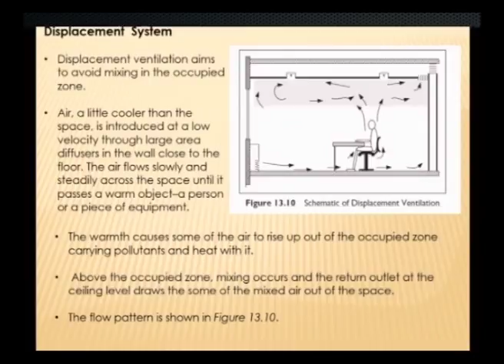The air movement in the space separates into a lower displacement zone with a recirculation zone above. In a well designed space, the recirculation zone is just above the occupied zone. So, the objective of the system is to have the occupants and the equipment in a flow of clean air with their own heat causing convection around them. This will lift their pollutants up out of the occupied zone. So, usually the pollutants will start mixing only above the occupied zone. So, naturally the occupants get only clean air.